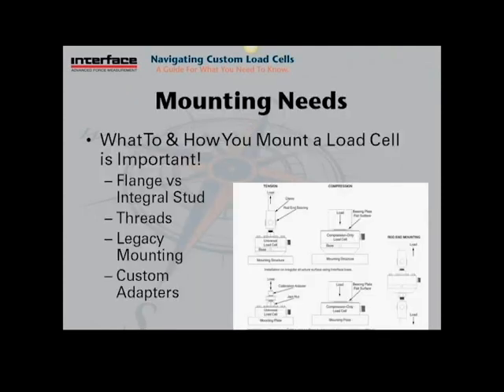Now we're going to talk about some mounting needs or considerations. We have several options as far as mounting that we've assisted customers with in the past. So on either end, you may have male or female threads, thread adapters similar to what we use in the 1600 load cells, integral studs, which is similar to what we have in the 1800 series load cells. We have a flange mount series, which are typically used on cylinder applications, and you can also use clevises or rod end bearings in tension applications.